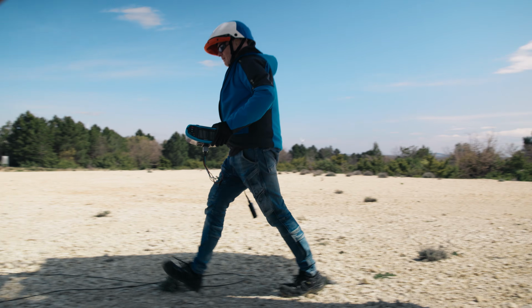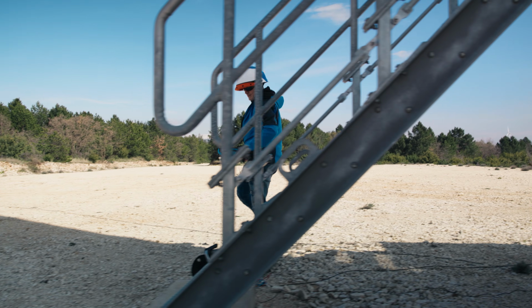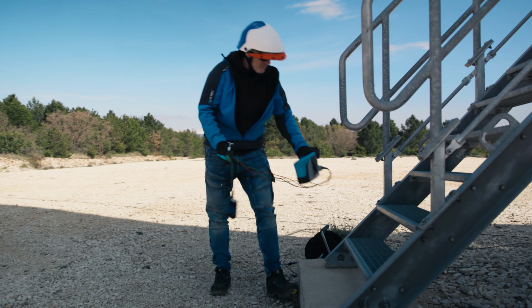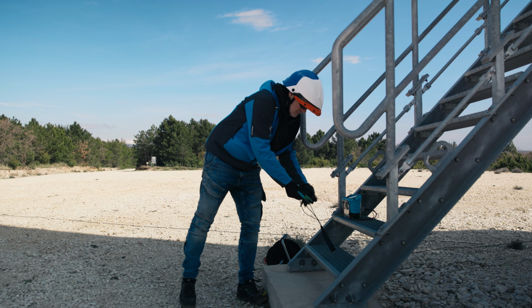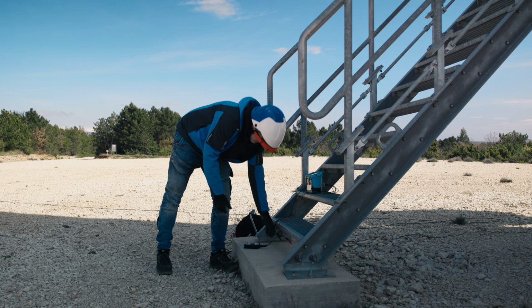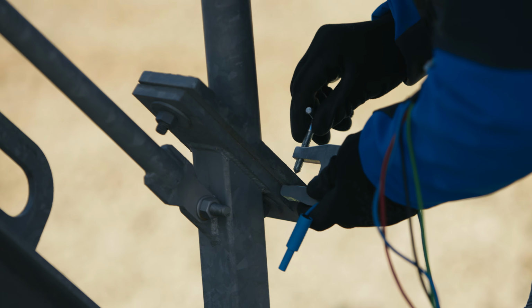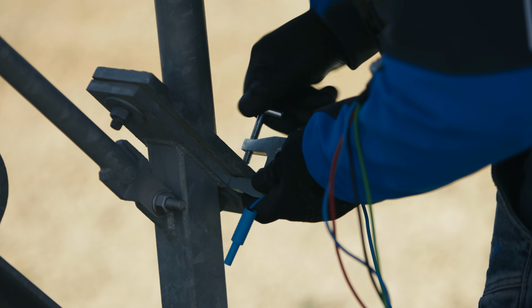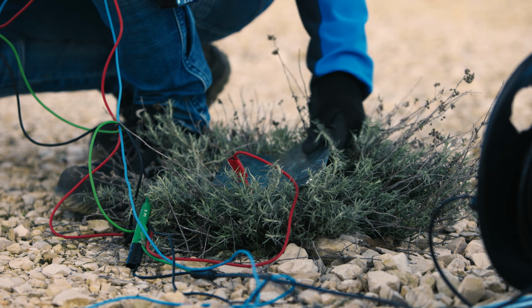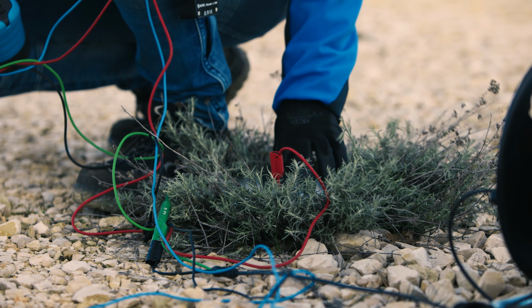The generator section of the measuring instrument, such as the Metrel MI3288 or the MI3290, is connected between the turbine base and an auxiliary probe using the reel's black and blue wires. To measure step and touch voltages, the green and red wires are used.